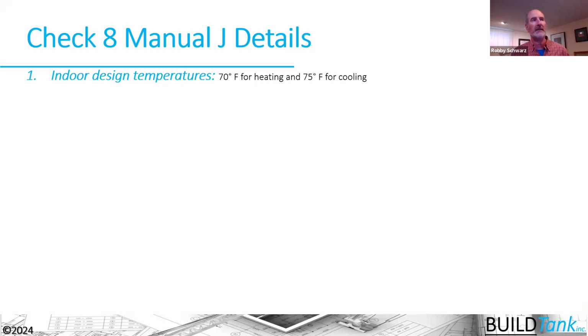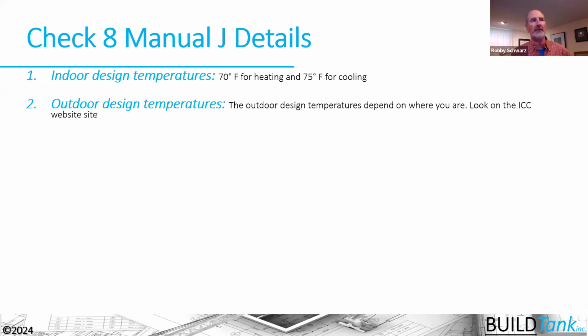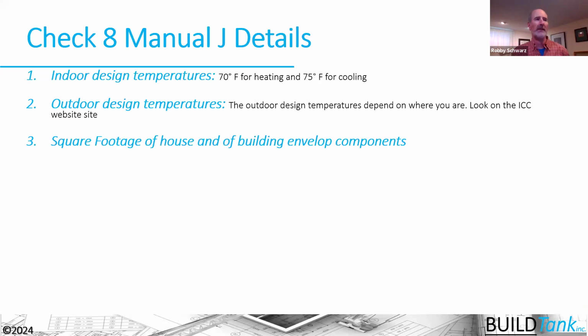Are some of the things that you want to look at and review on the Manual J to ensure that you're getting a proper Manual J, because you're going to see in a minute that some of these numbers can be fudged and we're going to get the wrong calculation. So we need to look at the indoor design temperatures. We need to look at the outdoor design temperatures. We need to look at the square footage of the house and the building thermal envelope components to make sure that we've done a proper takeoff of that house.